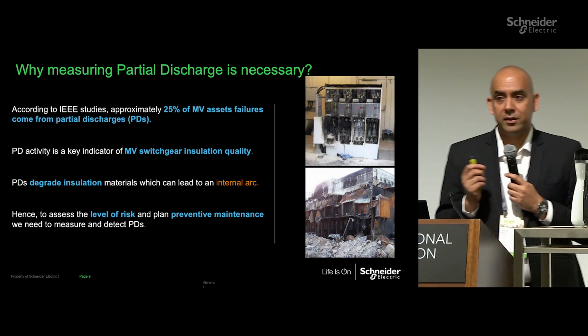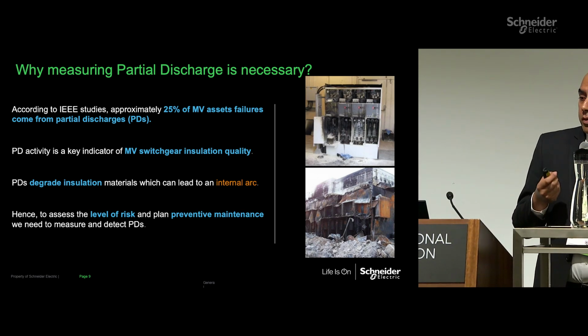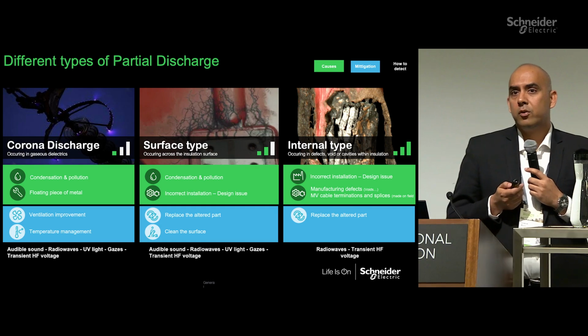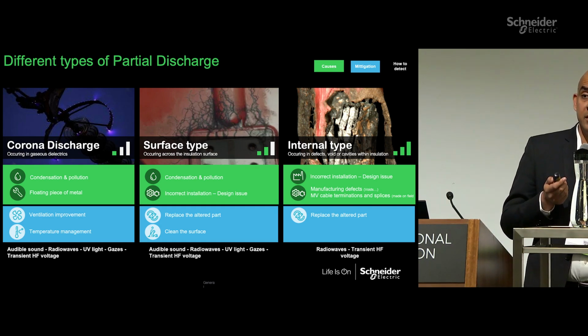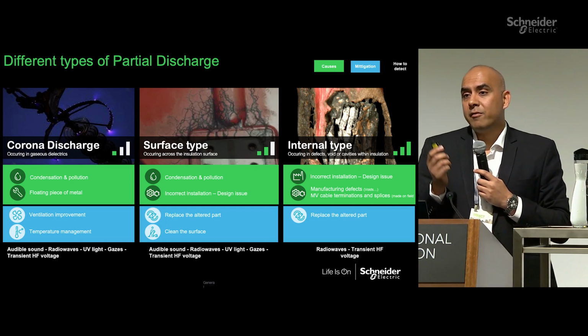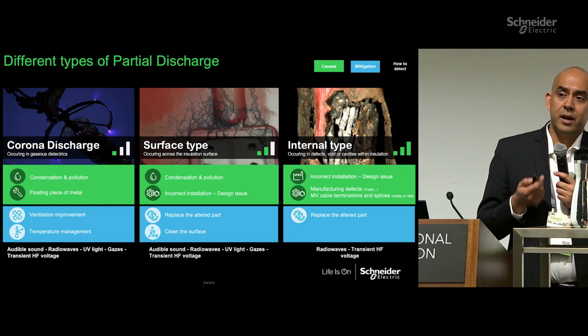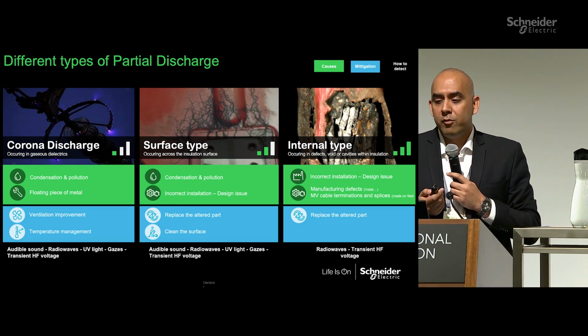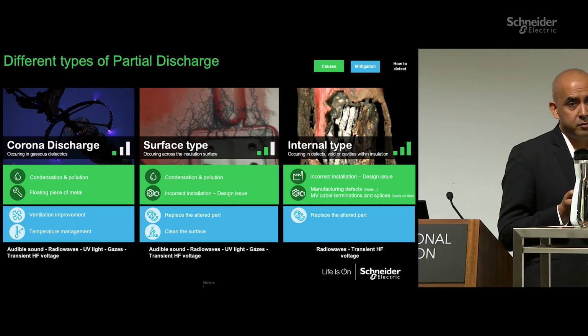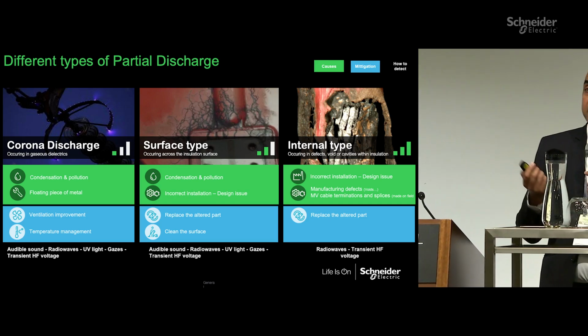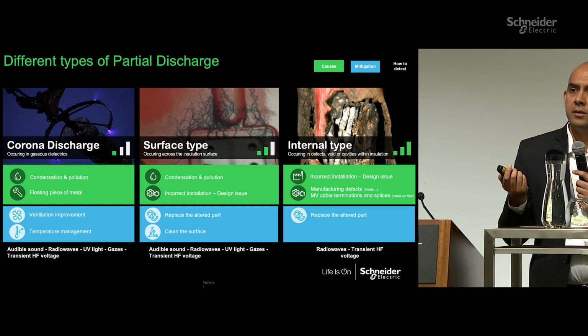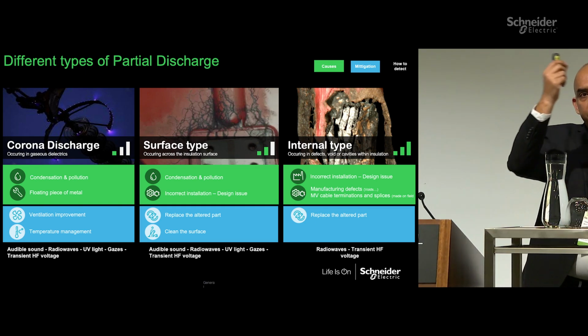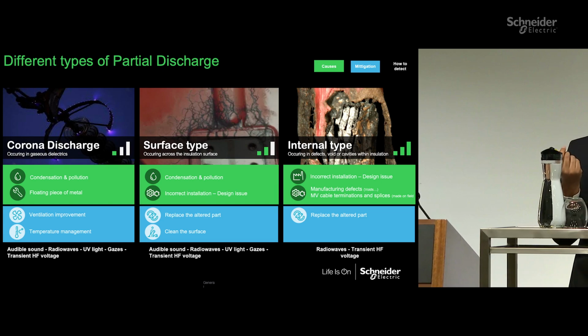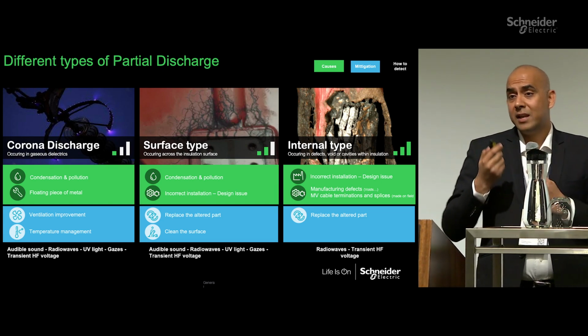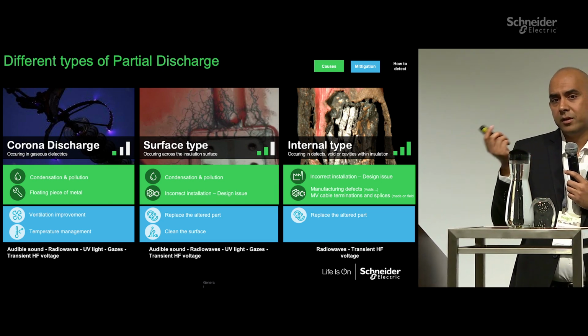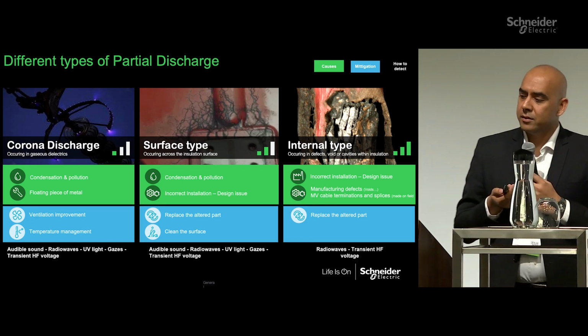And there could be various types of partial discharges. And this is where the monitoring becomes very, very critical, because not all partial discharges can be detected very easily. And different types have different effects and risks on the systems. So one very basic type of discharge, which probably we have seen in high voltage or outdoor substations, is the corona discharge. You would have seen the blue light, the arcs probably coming in outdoor substations when a switching happens. This basically happens in air or in the insulation medium. It could be in gases when you have a GIS.